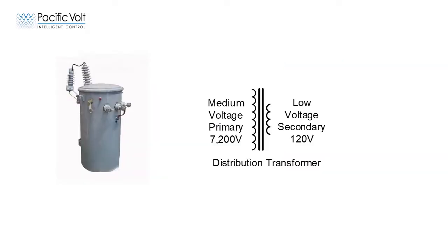In North America, every building is connected to the electrical grid through a distribution transformer. The medium voltage feeder line, which runs down your road, is typically 7,200 volts. Buildings operate at low voltage, which is limited to 600 volts or less. The transformer divides the medium voltage on its primary side down into something usable, like 120 volts on its secondary side, before it is supplied to the building.